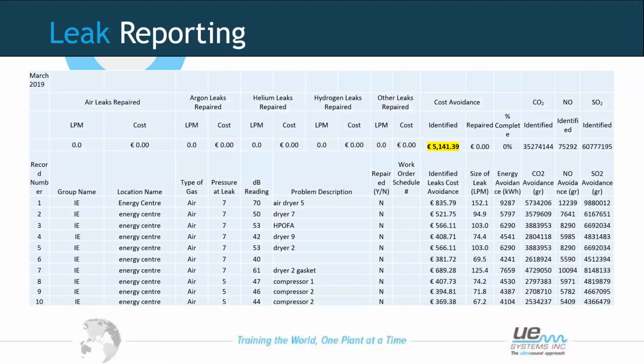This took about half an hour, I would say, when we did this little 5-10 leaks in one area. And again, as long as we understand how much a site is paying per kilowatt hour for the energy, we understand the running hours of the compressor systems, and we identify what the pressure is at that point of the leak, then we can actually quantify that. So then we can show what potential savings we can have per year on repairing those leaks.